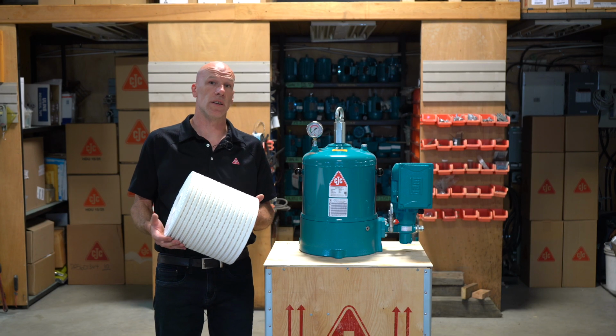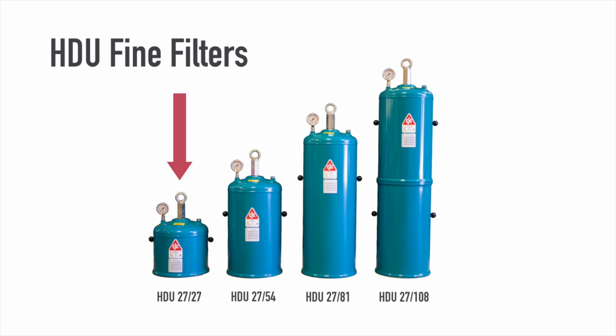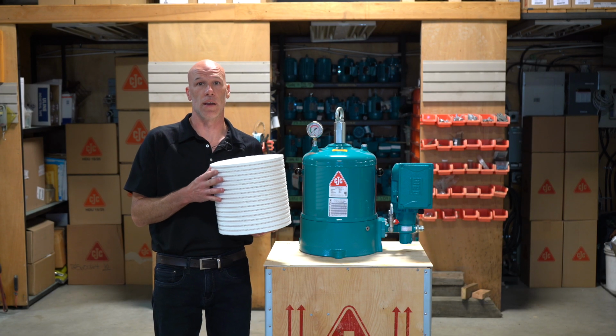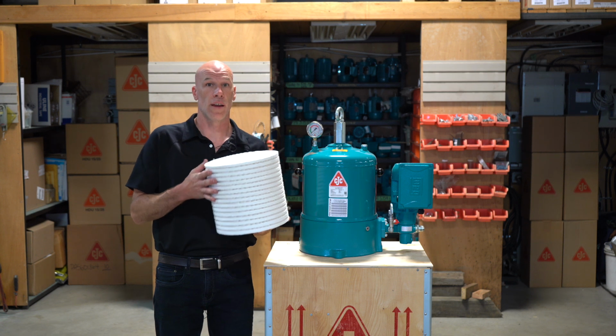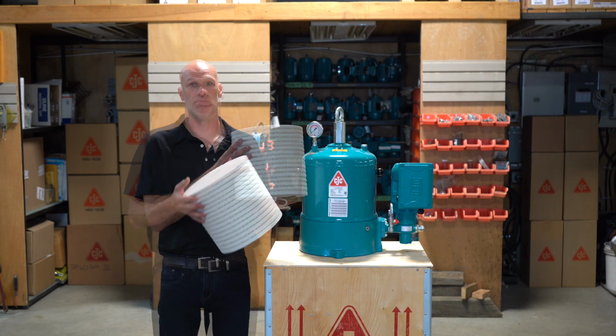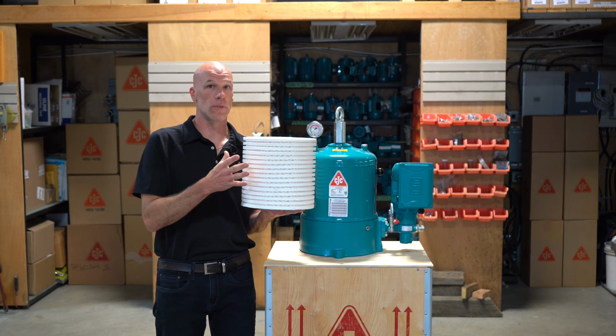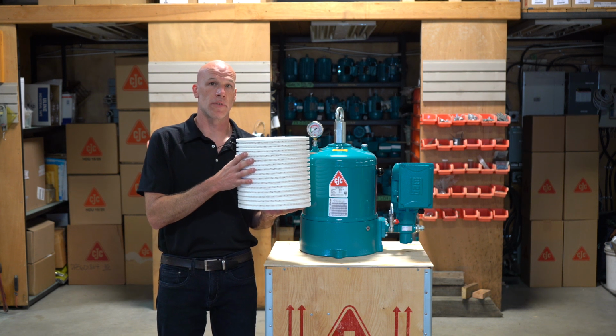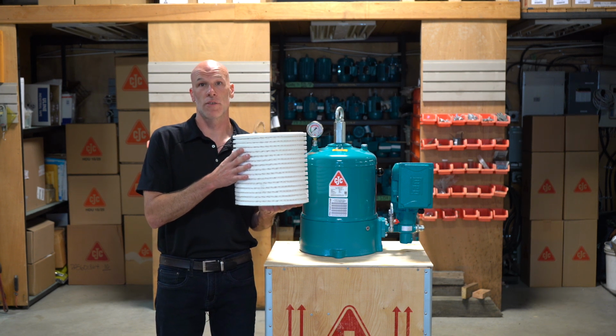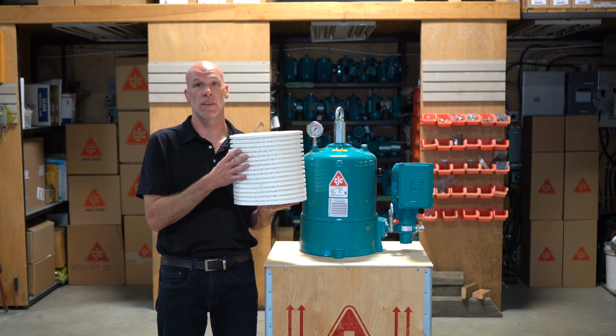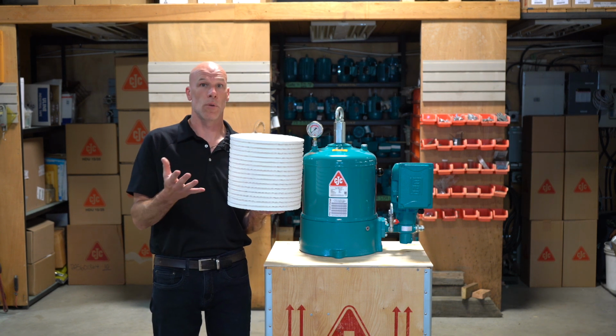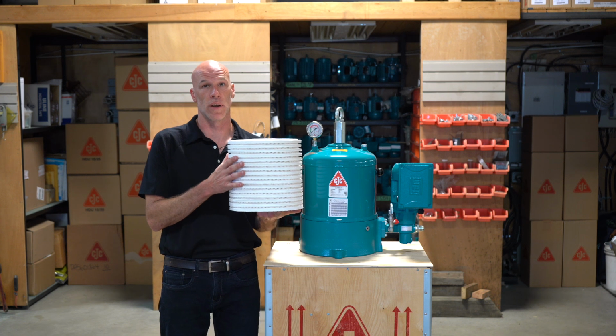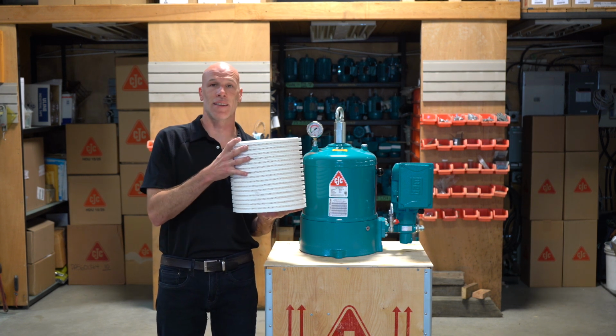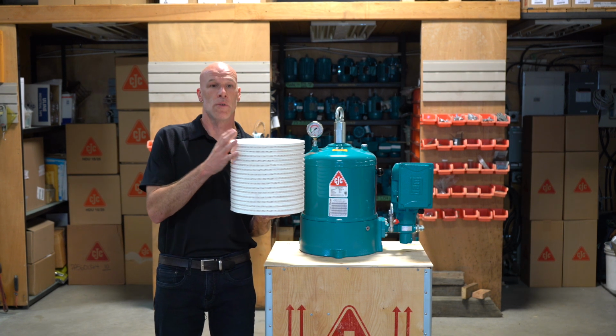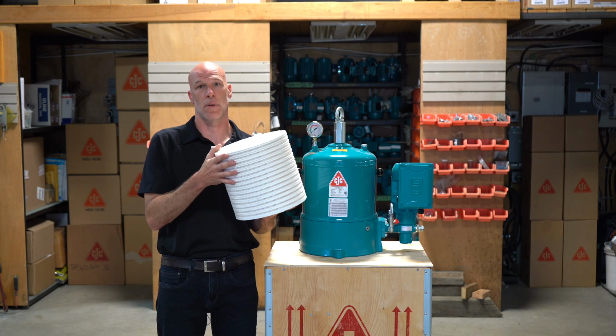The 2727 is part of the HDU fine filter family, which uses high-efficiency cellulose media to capture solid particles, water, and varnish degradation byproducts. The 2727 filter insert we use in the HDU filters to 3 micron absolute, and it has also a tremendous holding capacity between 5 and 7 kilograms of solid particles. It will also absorb moisture up to 2 liters in one insert. And the varnish, because it's taken into the fibers of the cellulose, we have so much cellulose that it has a massive capacity for holding and retaining varnish.